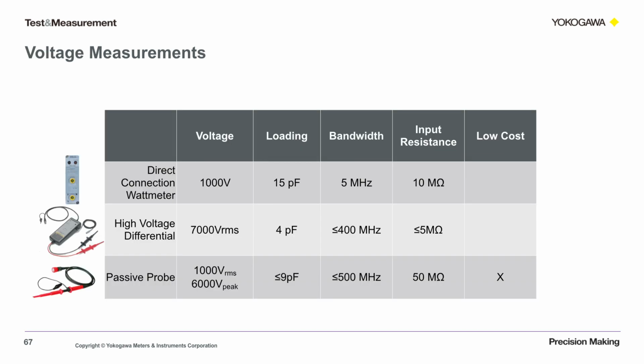We've determined we need to calculate voltage and current to make any power measurements. Voltage measurements are taken in parallel. There are a few methods for making these measurements, each with trade-offs. The first is the wattmeter. This wattmeter is taken from our WT5000. It has voltage inputs on the top and current inputs at the bottom.